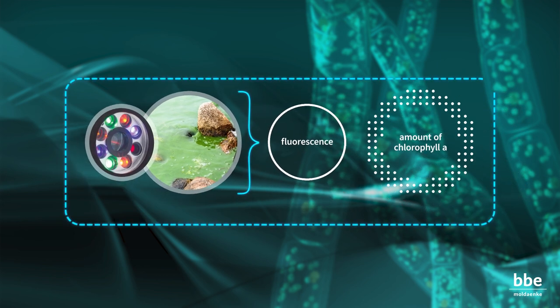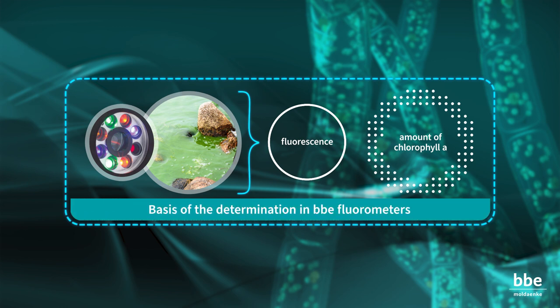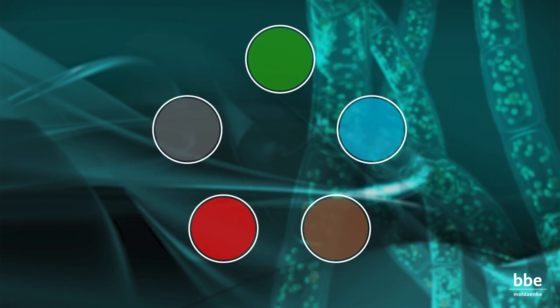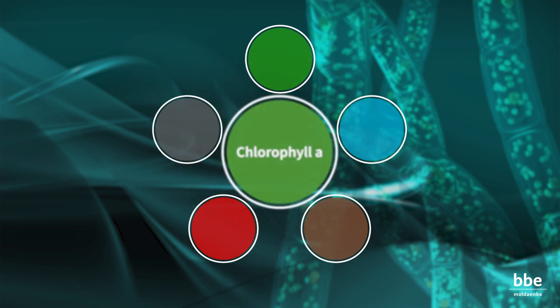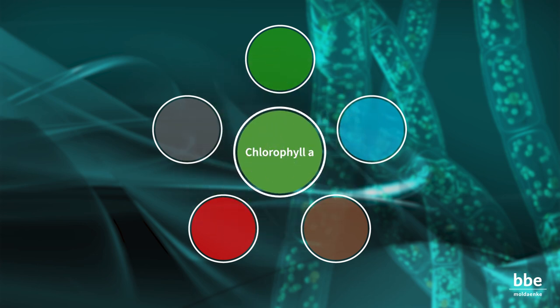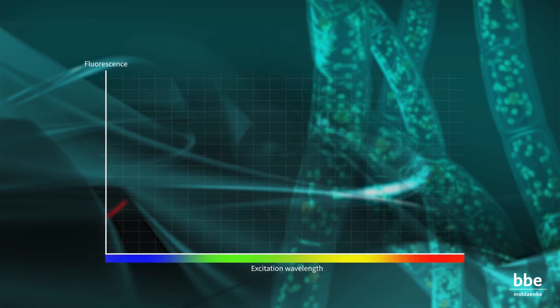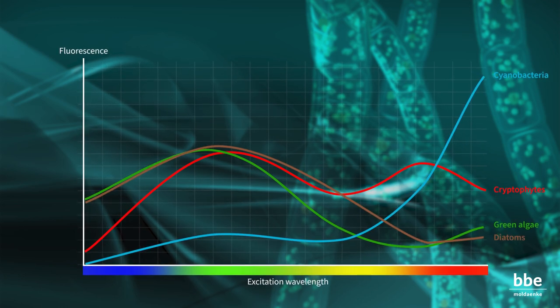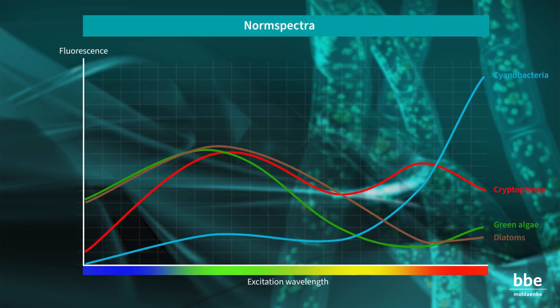This method is the basis of the determination in the BBE fluorometers. Five main spectral classes can be identified, which are related to the different algae pigments. These pigments cooperate with chlorophyll A to transfer the energy of the trapped light. Each class has a characteristic pattern of fluorescence at defined excitation wavelengths, termed the norm spectrum, which enables the fluorometer to identify different algae in a sample.